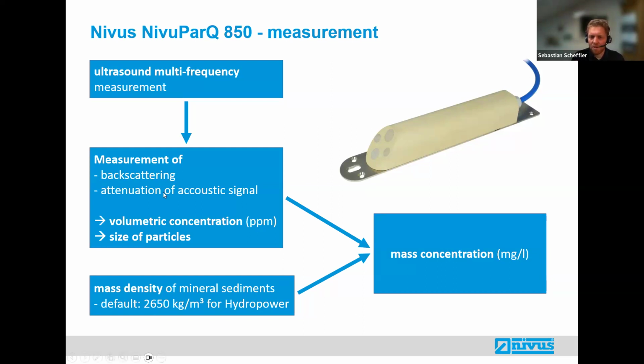With these two parameters, we get information about the volumetric concentration of particles in the water, and also about the size of particles. So we get the volumetric concentration in ppm, parts per million, and information about the particle size distribution. Then we have to enter a mass density in the transmitter, in the unit. For hydropower, we use the default value of 2,650 kilograms per cubic meter. That's the value of the quartz mineral.